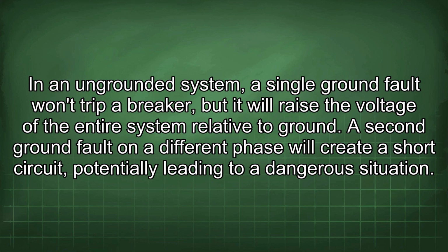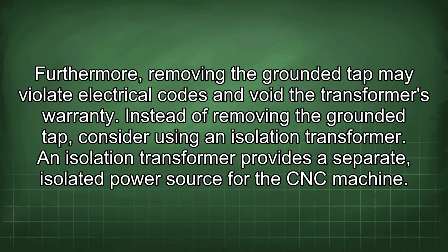In an ungrounded system, a single ground fault won't trip a breaker, but it will raise the voltage of the entire system relative to ground. A second ground fault on a different phase will create a short circuit, potentially leading to a dangerous situation. Furthermore, removing the grounded tap may violate electrical codes and void the transformer's warranty.